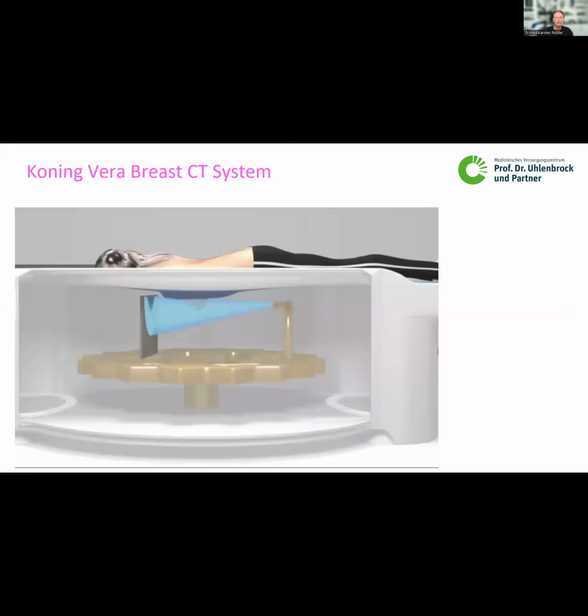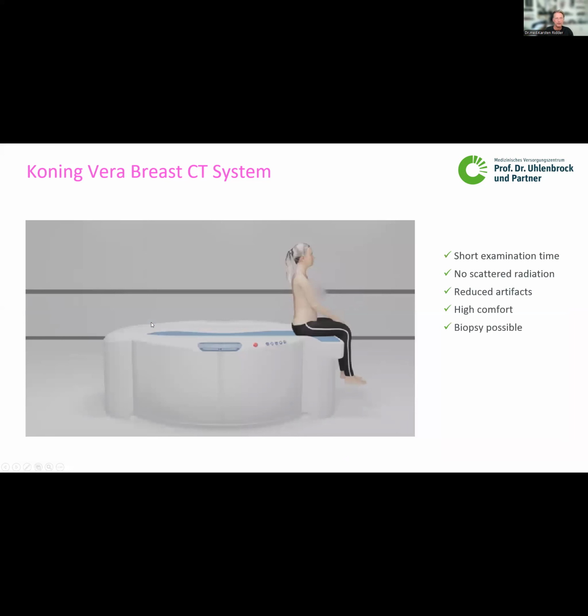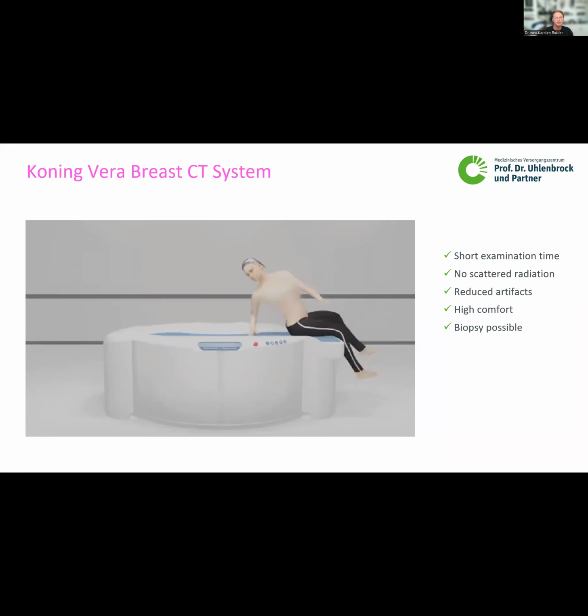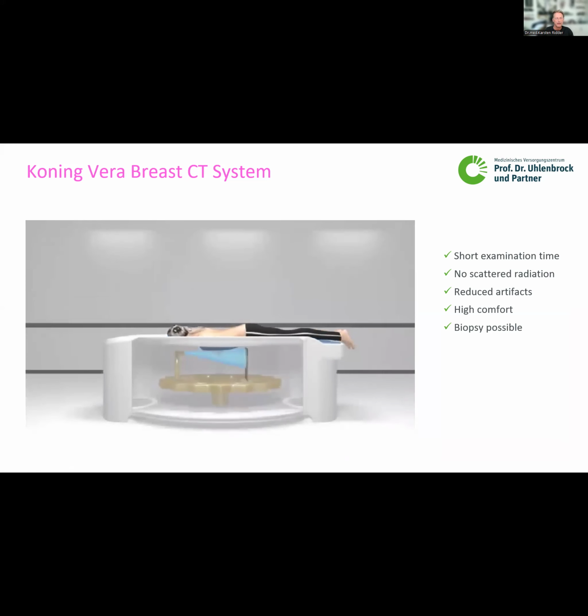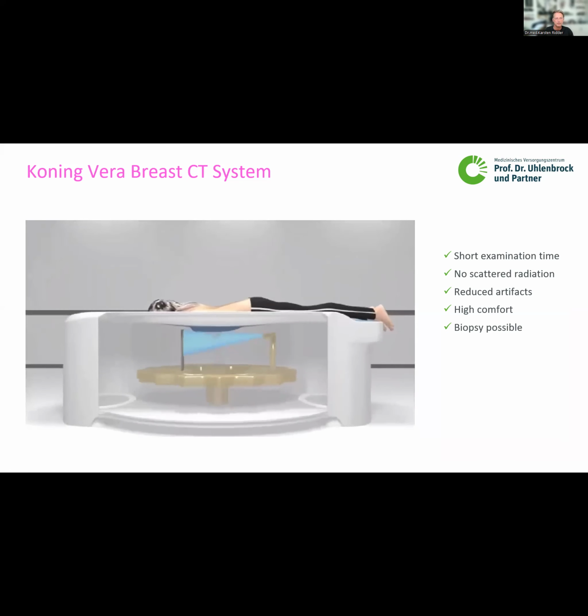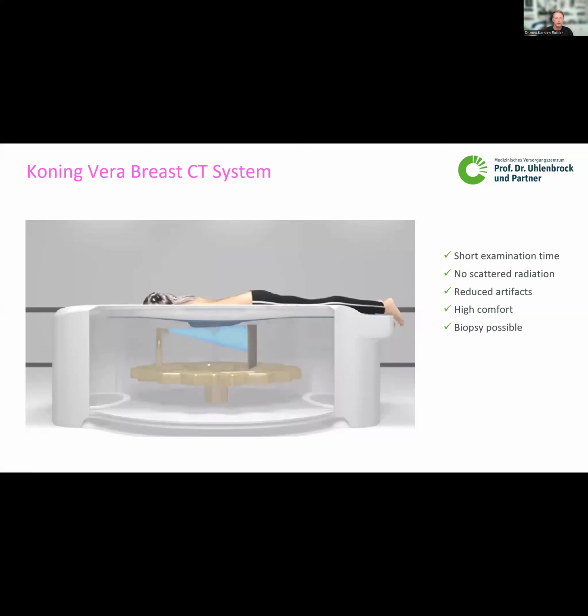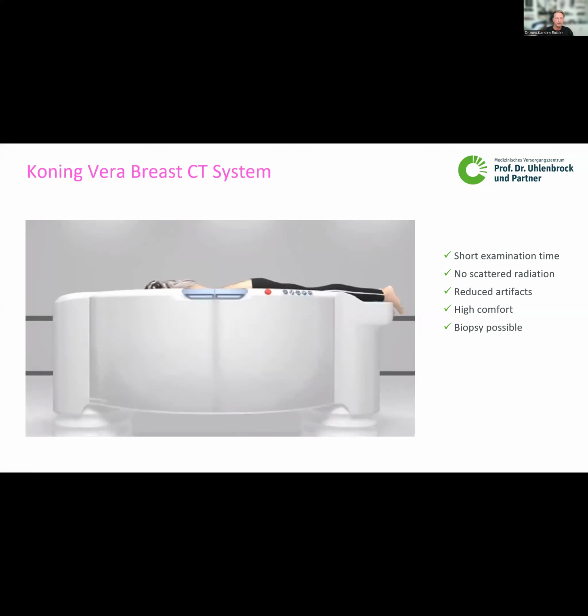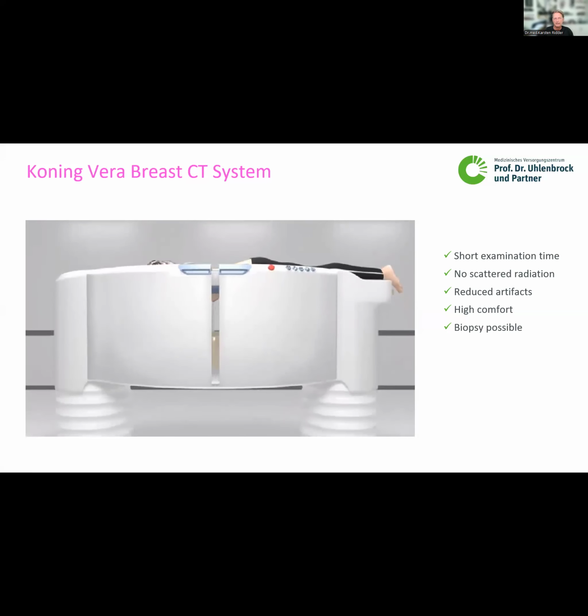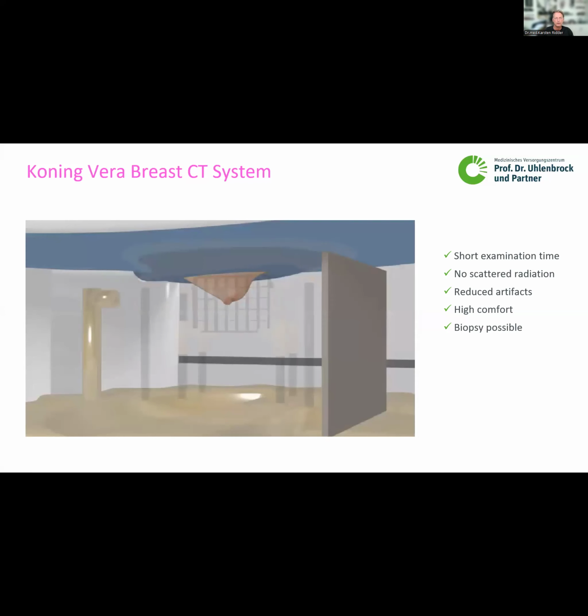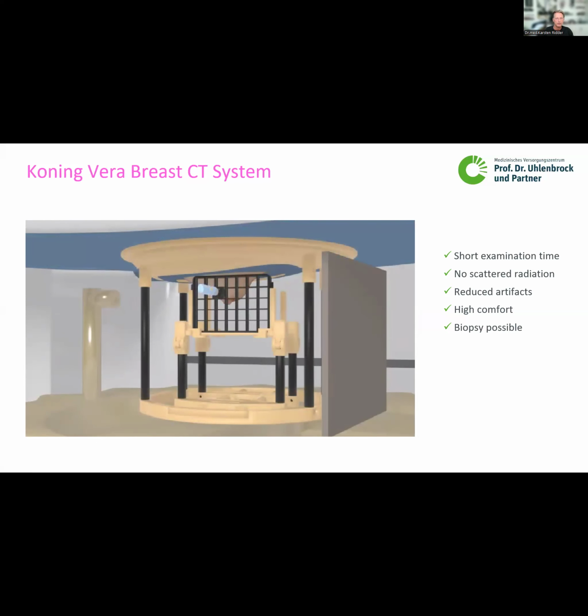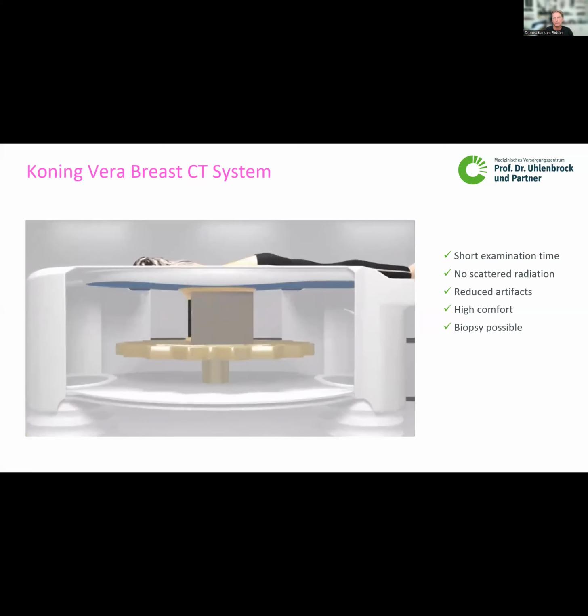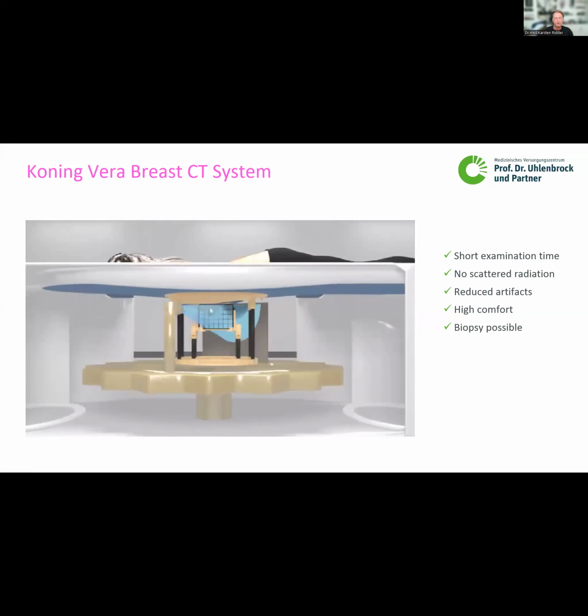On the other side, the Koning Vera breast CT system is a cone-beam CT system with a source and a detector. And in the video you see here, the patient is also positioned the same way in a prone position. And then there's one round the device takes, also about 6 or 7 seconds, quite short. And then the images are done. The advantage of this system is that you can do biopsies. They have a device which is mounted into the machine where you can do stereotactic or even 3D biopsies of the breast to take a closer look at microcalcs or other tumors. So quite interesting, well working.